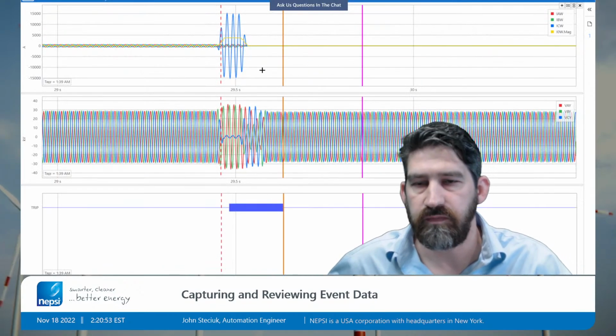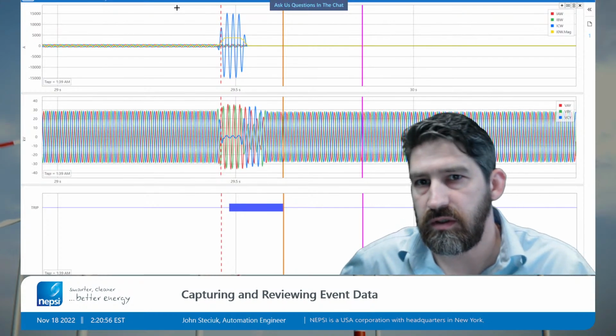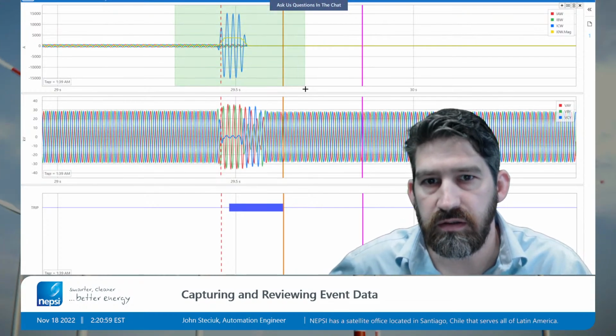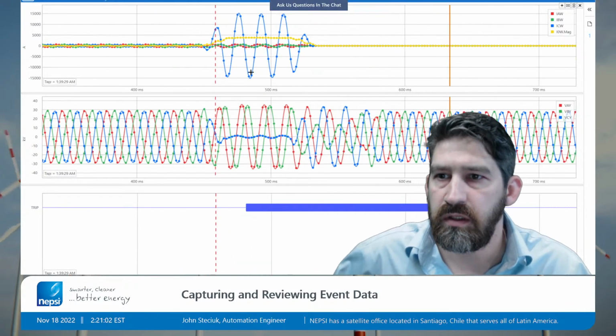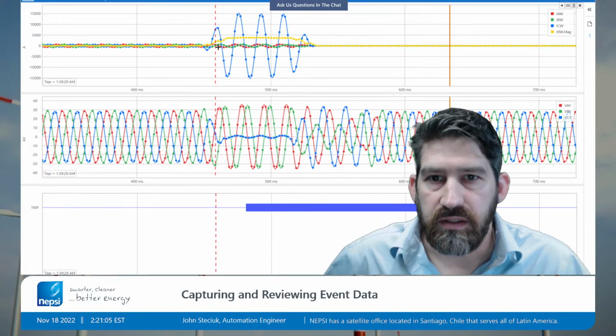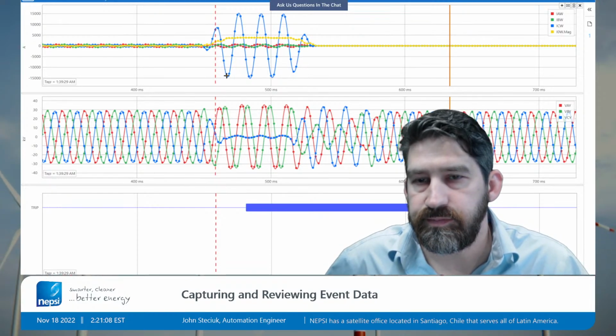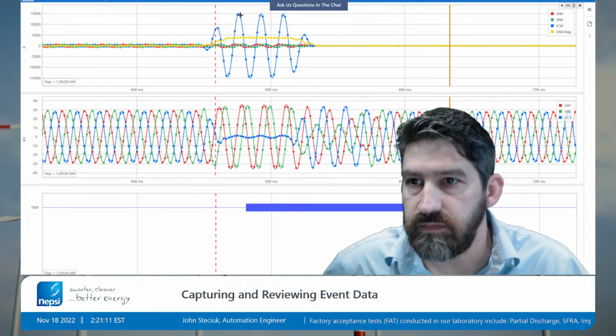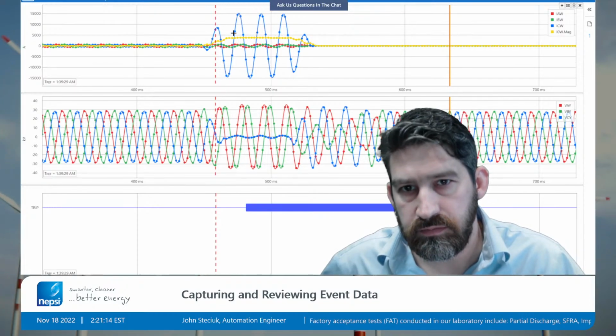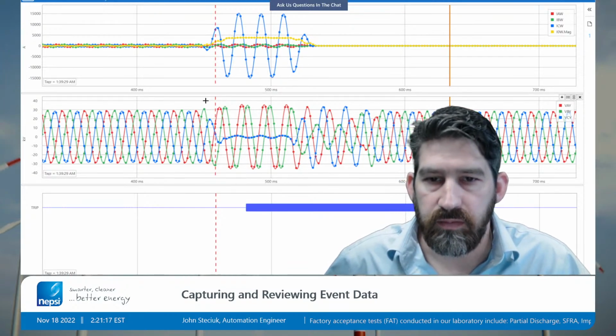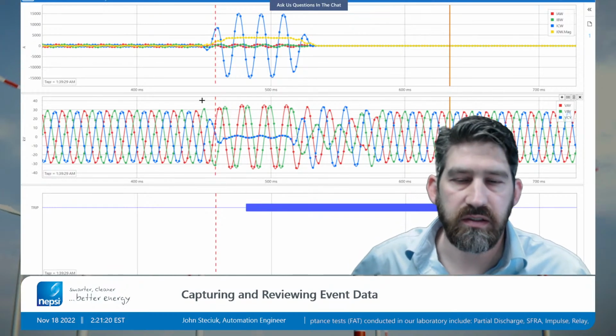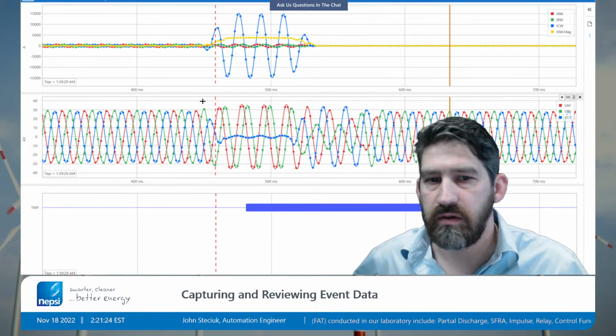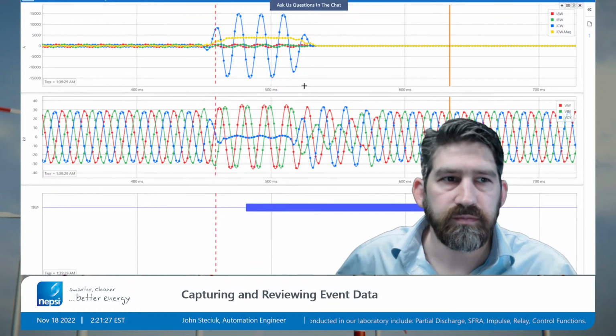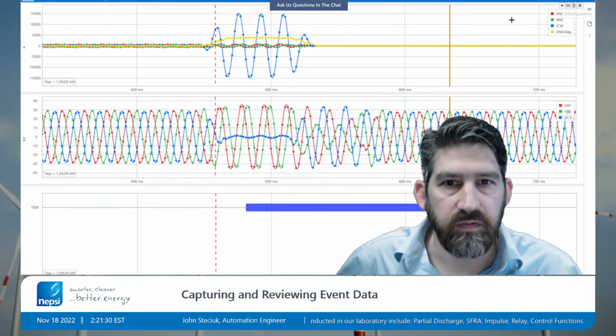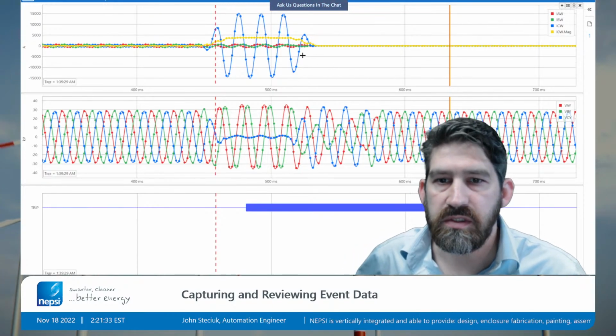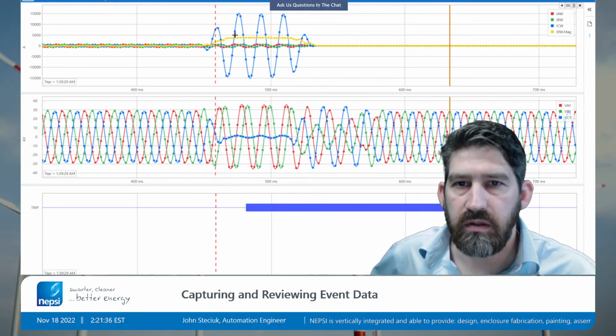Alright, so this one we have a phase to ground fault, and I'm going to zoom in a little bit on the event here. You can see C phase current is amplified and up to about 15,000 amps. It's real simple to see which phase it was and how high the current had gotten. You can add different values here to see other analog data.